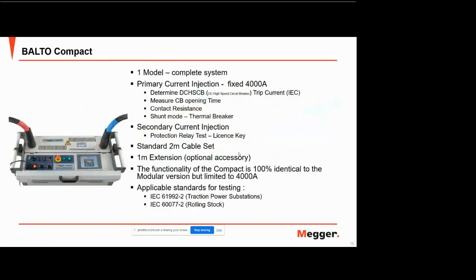The other Balto that we have in the product range is the compact. So the modular, as we said previously, goes up to 40,000 amps. The compact is fixed at 4,000 amps. And this is typically used for rolling stock applications where the current required to test the breakers in a rolling stock are far lower than the traction power substation. The compact, however, does exactly the same types of tests that the modular does. It does the trip current, it does the opening time for your circuit breaker, it does the contact resistance, and it also does the shunt mode for your thermal breaker applications. But the output current is fixed at 4,000 amps and cannot be extended beyond 4,000 amps, unlike the modular, which can be extended.